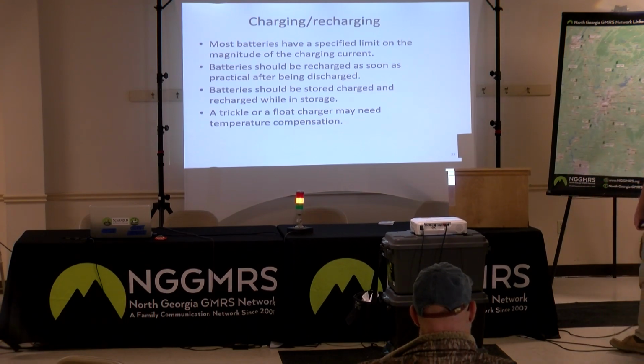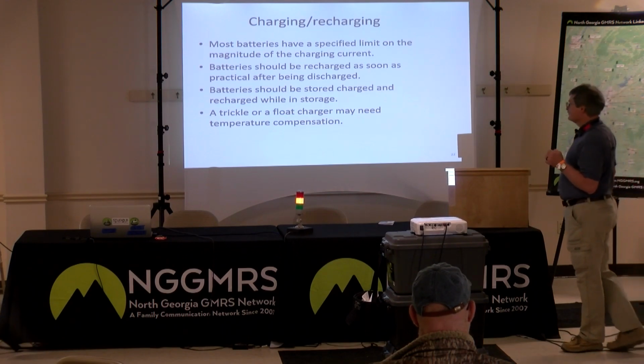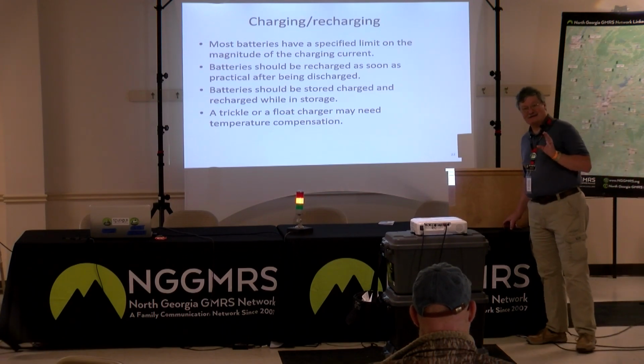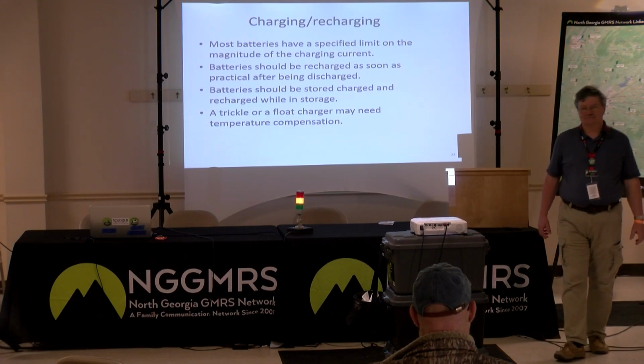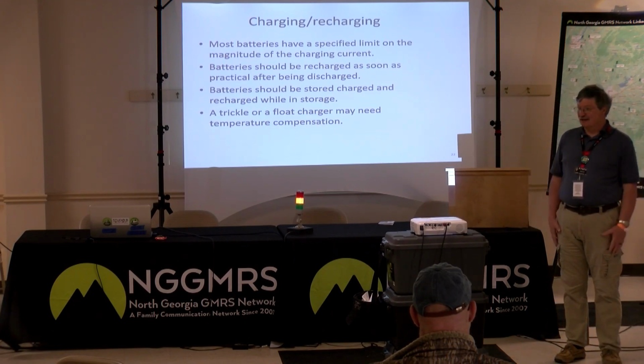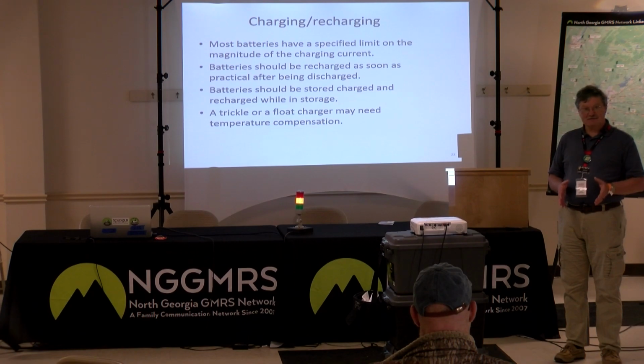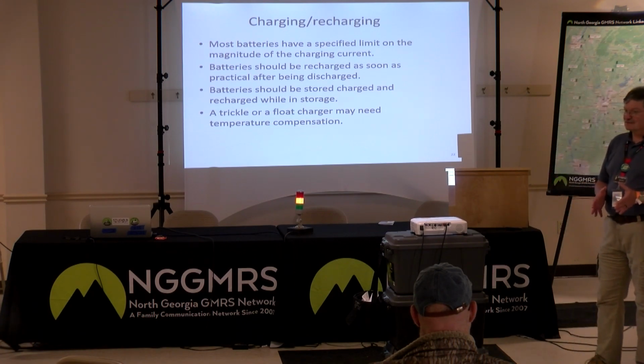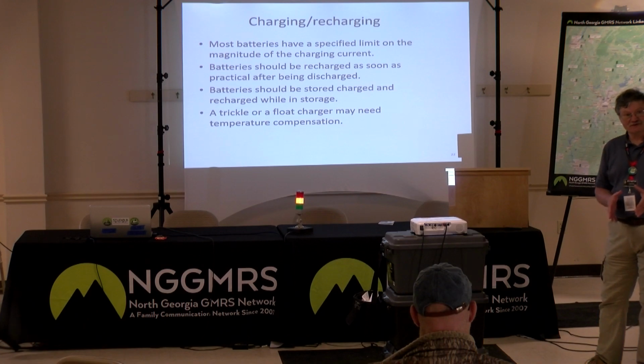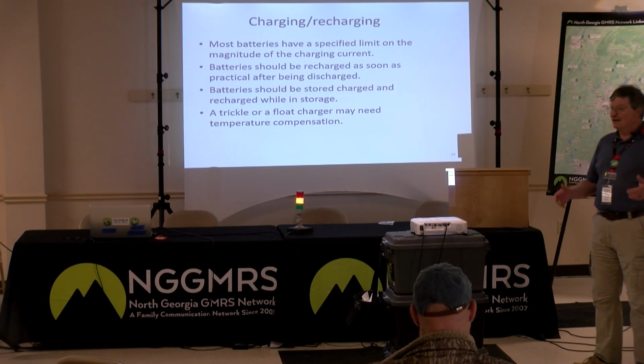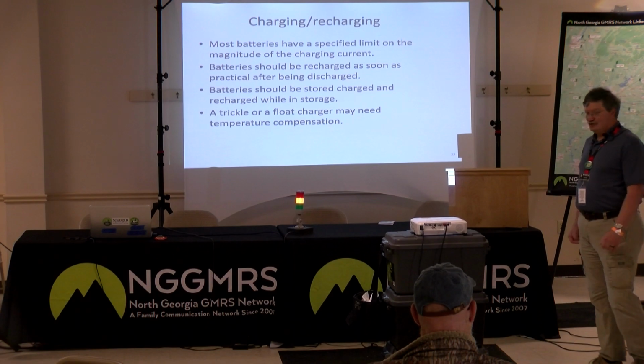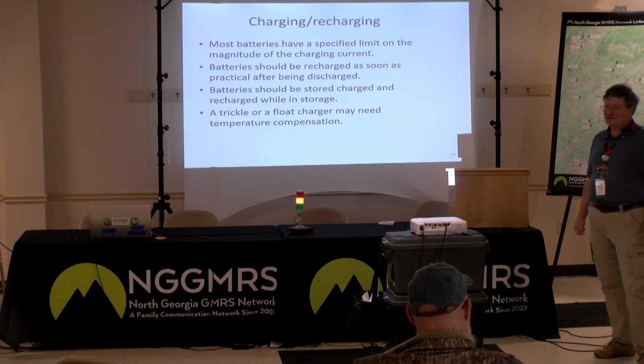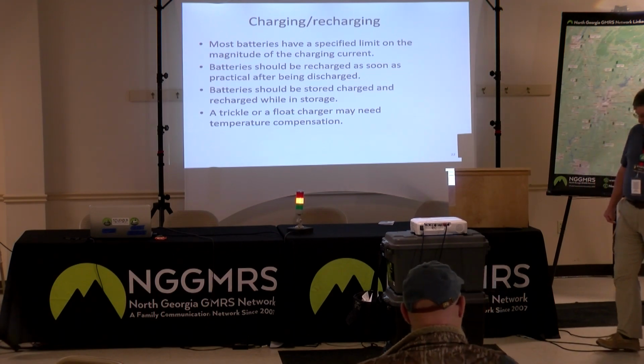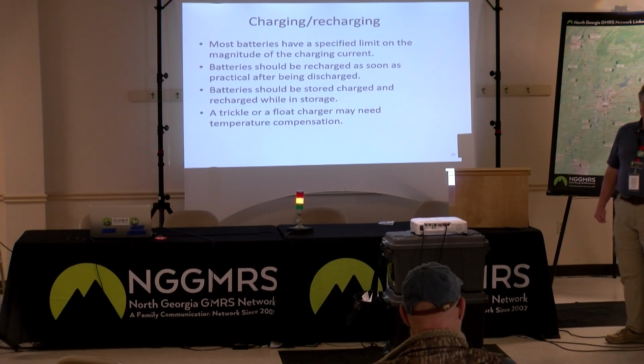Batteries should be recharged as soon as possible after they're discharged, or as soon as practical. Why? That's my backup power source, right? The event's over. I don't want to leave it sit, because what if another event happens two days from now and I wasn't going to recharge it for a week? Well, you have gotten caught in a very touchy situation, because you're not prepared now.